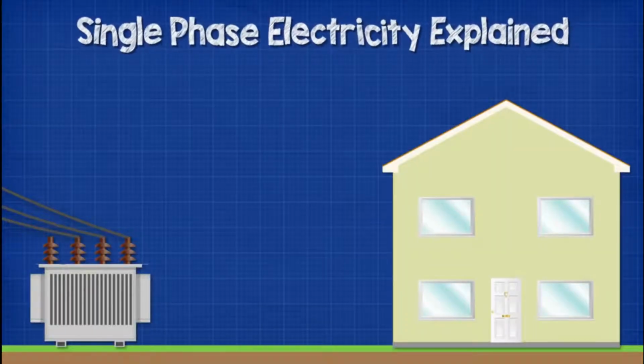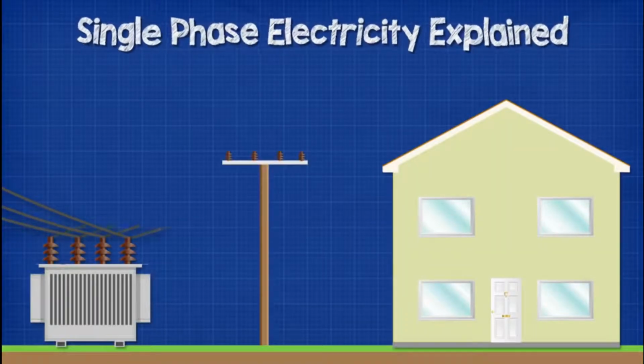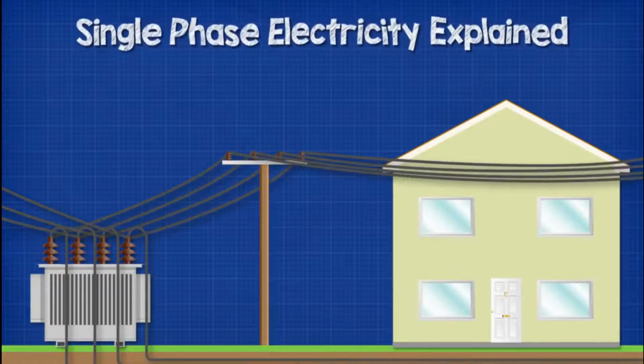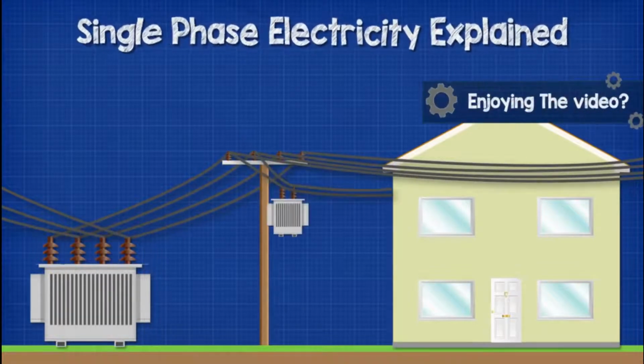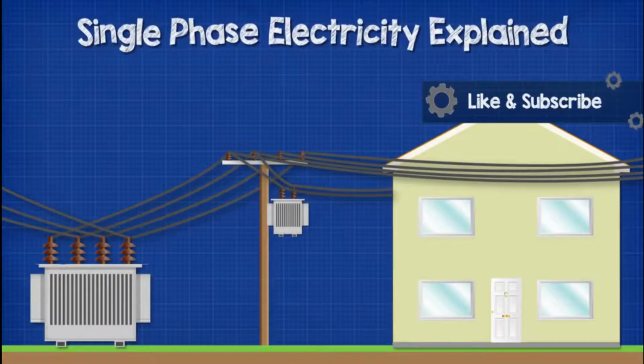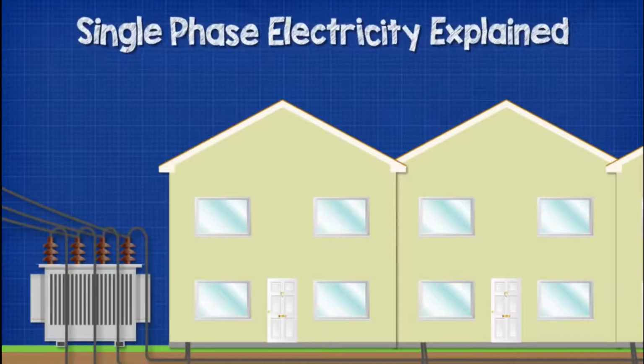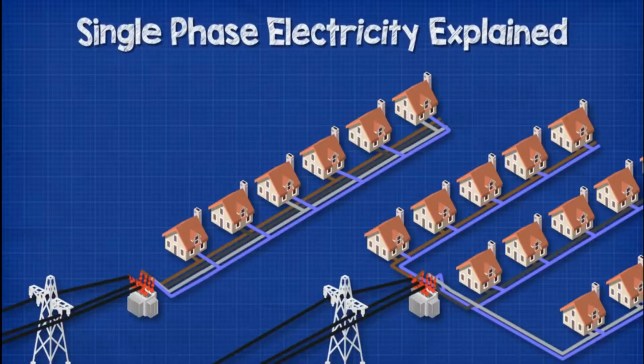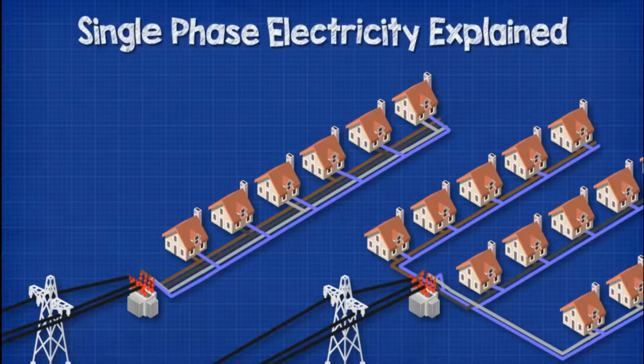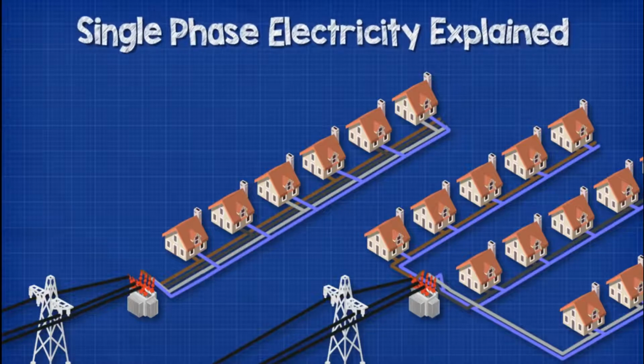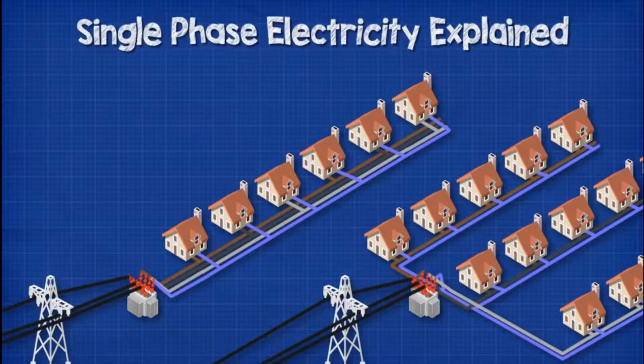From the substation, the electricity will be distributed locally through either overhead or underground cables. Depending on the local design and the voltages being used, a home might be connected directly to a small transformer located close to the property, or alternatively, a group of houses will share a larger transformer. Now, each house in a street might be alternately connected to a different phase, or different streets might be connected to different phases. This is just to try and balance the demand on the transformer.